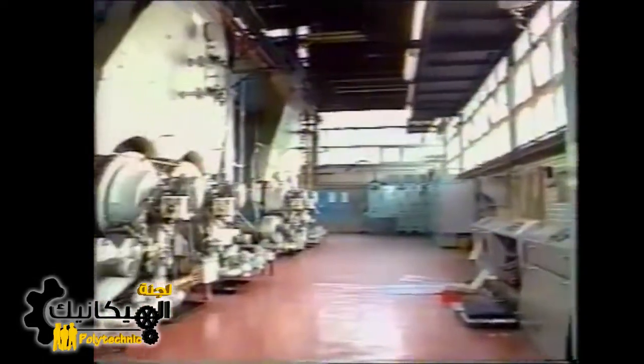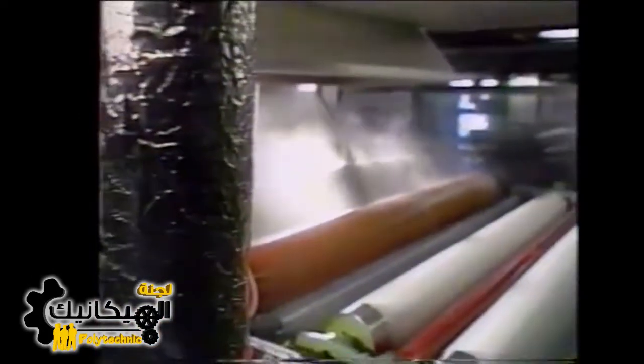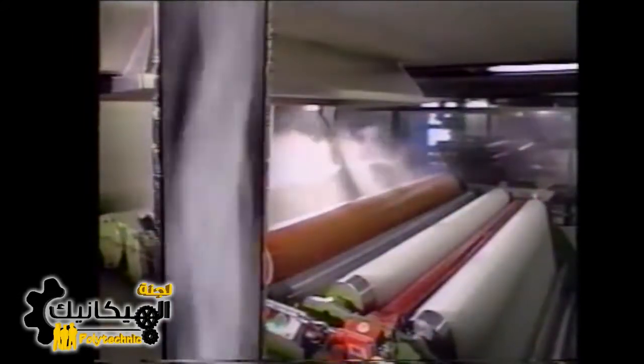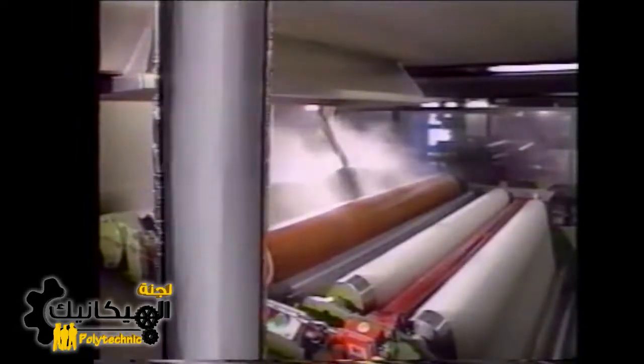All of the tests so far have been conducted in almost ideal conditions, with a steady, light steam load. However, in reality, steam demand is rarely steady. It comes in peaks and troughs, and a boiler must be able to respond to these changes. Whenever the steam demand increases, it will take a little time for the boiler to raise its output to match the new demand. However, during this transition period, more steam is being used by the plant than the boiler is producing, so the total amount of steam in the system falls, which causes the pressure in the system to drop.